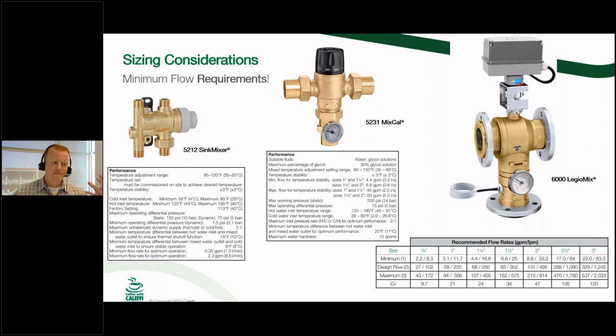And I've got to listen, I've got to hear them out and everything like that. But my first thought is that obviously the common denominator here is not the mixing valve anymore. Okay, you've replaced it 3 times. Let's look somewhere else, and that's why they're calling, obviously.